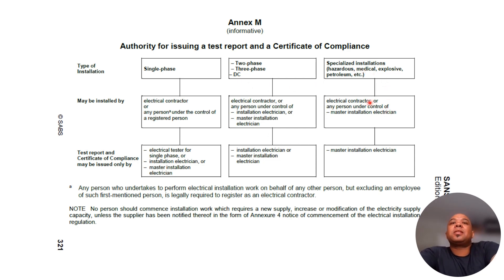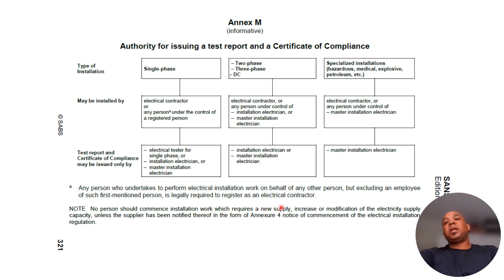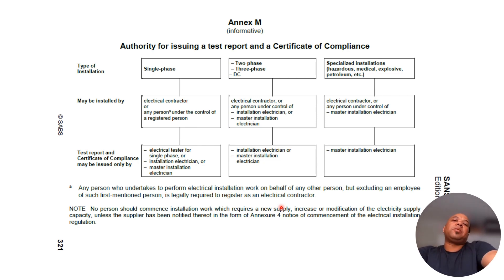I won't go too much into specialized installations, which cover medical, explosive, and petroleum environments. But importantly: any person who undertakes electrical installation work on behalf of any other person — excluding an employee of that person — is legally required to register as an electrical contractor. That's in the Electrical Installation Regulations and SANS 10142. So soliciting an unregistered person to do electrical work for you is technically against the law.